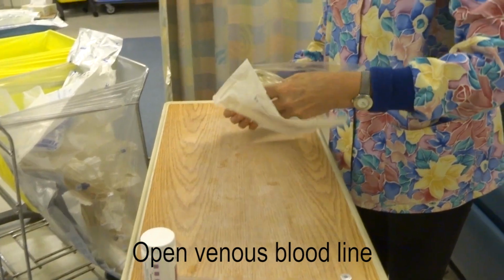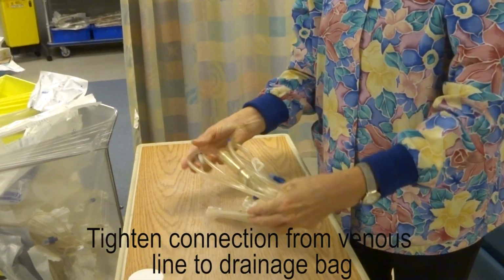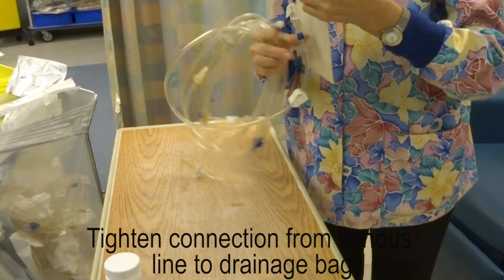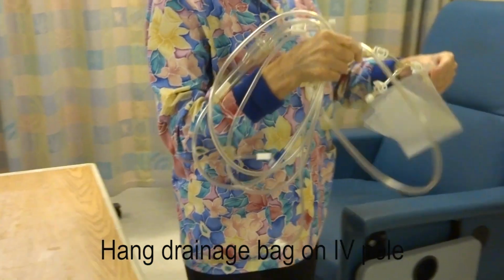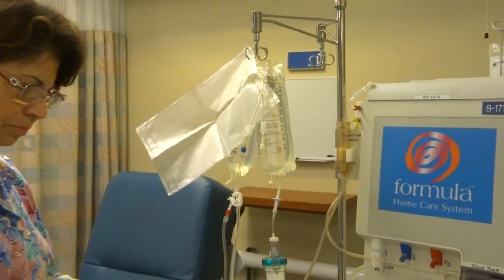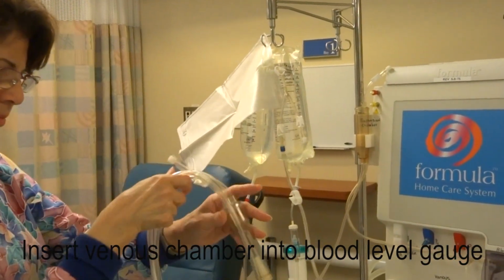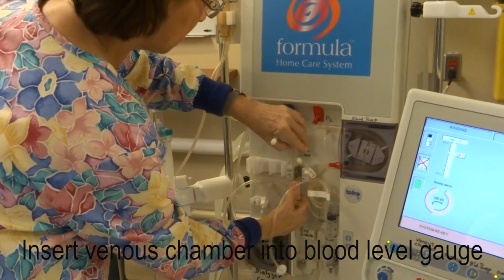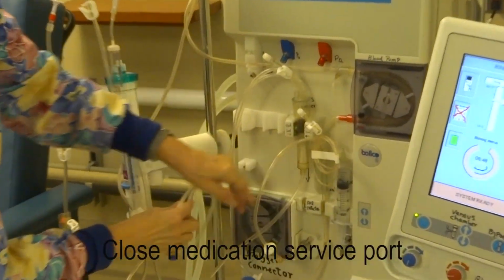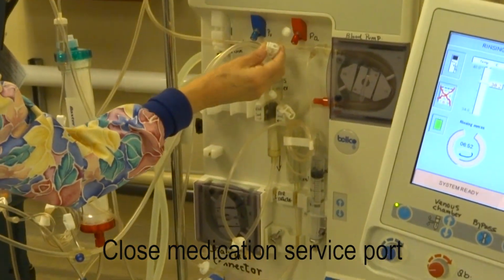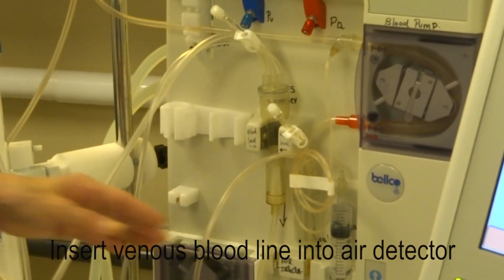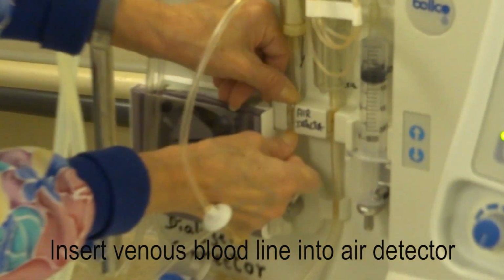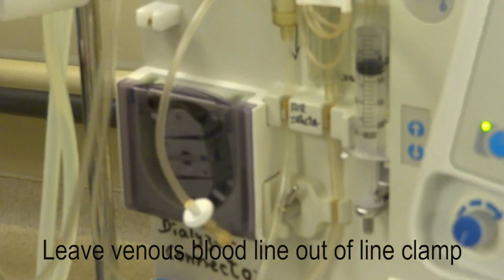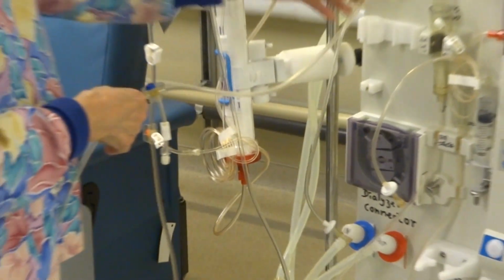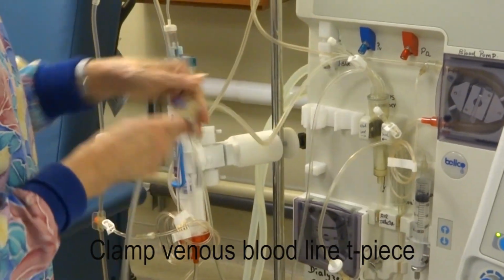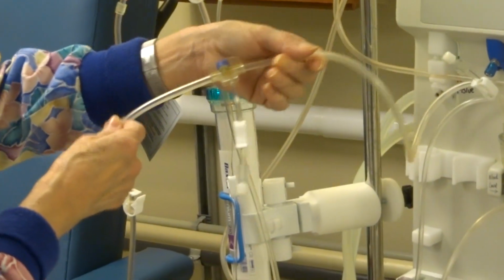Open the venous blood line. Tighten the connection of the venous line to the drainage bag. Hang the drainage bag on the IV pole. Insert the venous chamber into the blood level gauge. Close the medication service port at the top of the venous chamber. Insert the venous blood line into the air detector and leave the venous blood line out of the line clamp. Clamp the venous blood line T-piece located in the middle of the venous blood line.